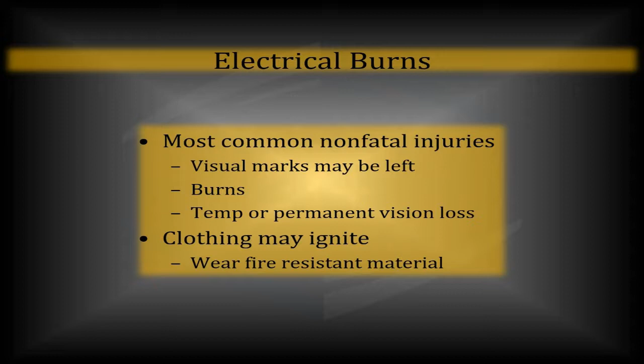Other forms of burns are caused when high amperage current travels through the air, like an arc. Arcs can exceed 35,000 degrees Fahrenheit. That's astronomical. These temperatures, the intense heat and light, can damage the skin and eyesight, as well as virtually vaporize flame retardant clothing and the metal involved. When you look at some arc flash videos, you can see copper, steel, and aluminum vaporize and become molten and fragmented. They become like a bomb, only that bomb is at elevated temperature. So not only does the force of this stuff exploding out do damage, but the heat that travels with it is like a warm knife cutting through butter. It's pretty nauseating to think about.